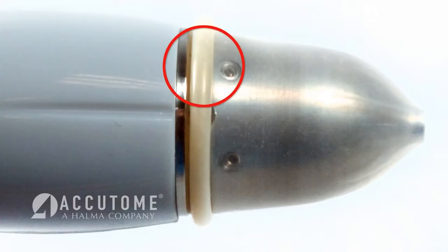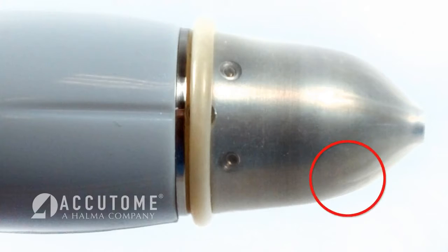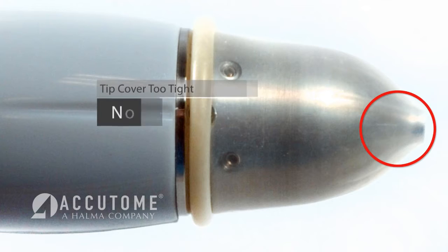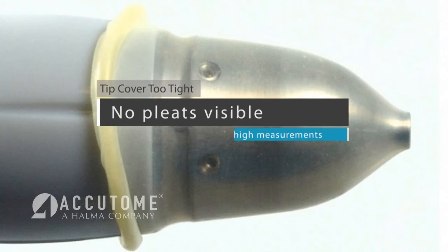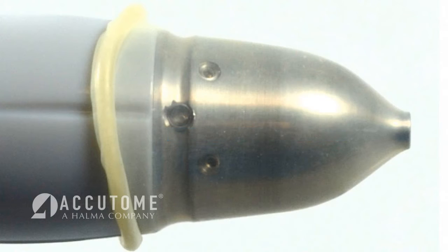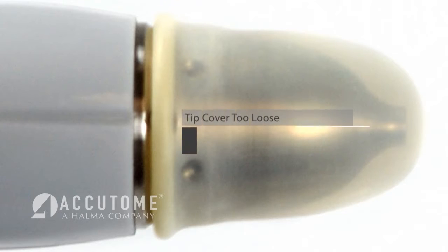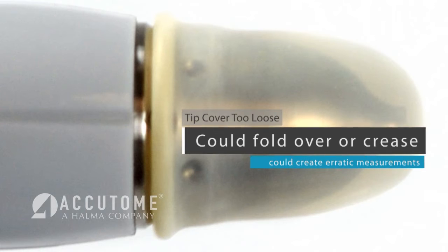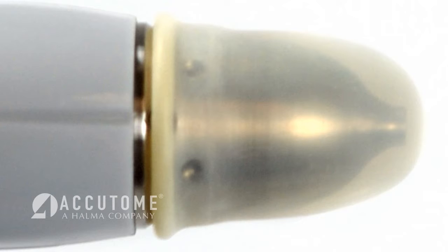This photo is an example of a properly placed tip cover. Pleats indicate proper tension while allowing the transducer tip to move freely. Tip covers that are too tight could introduce false resistance to the transducer pin and IOP measurements could read higher. Tip covers that are too loose can fold over or crease and possibly create erratic measurements with your accupen tonometer.